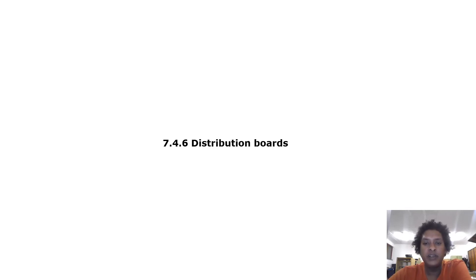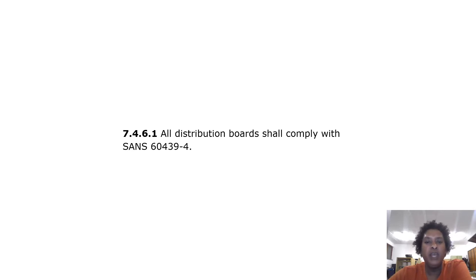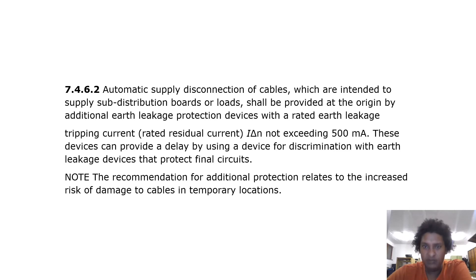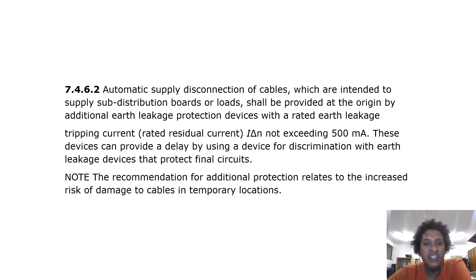Distribution boards. All distribution boards shall comply with SANS 60439-4. Automatic supply disconnection of cables which are intended to supply sub-distribution boards or loads shall be provided at the origin by additional earth leakage protection devices with a rated earth leakage tripping current not exceeding 500 mA. These devices can provide a delay by using a device for discrimination with earth leakage devices that protect final circuits. Note: the recommendation for additional protection relates to the increased risk of damage to cables in temporary locations.